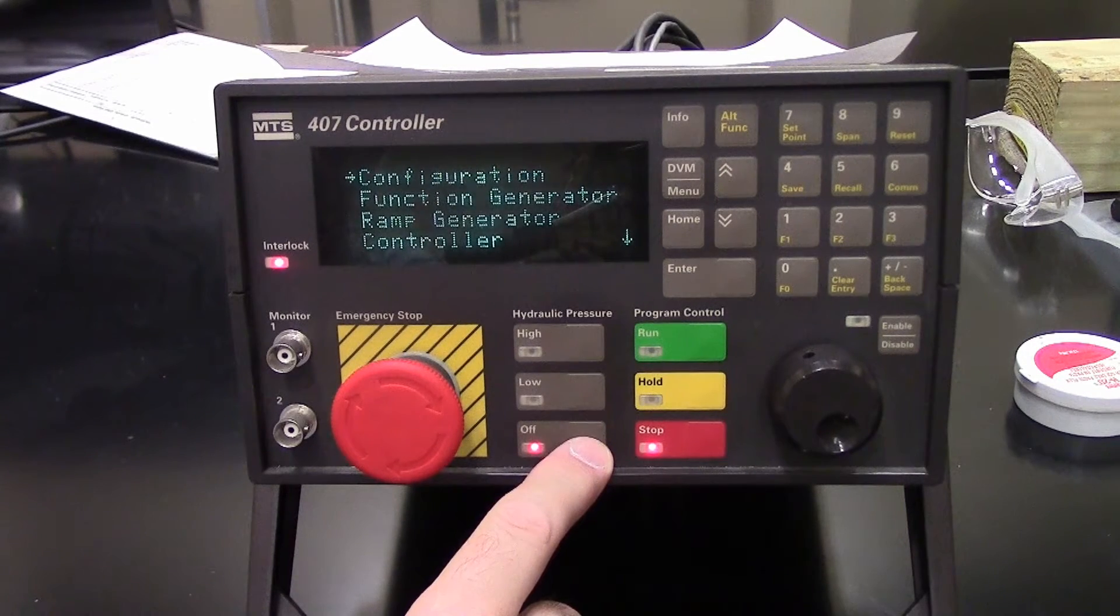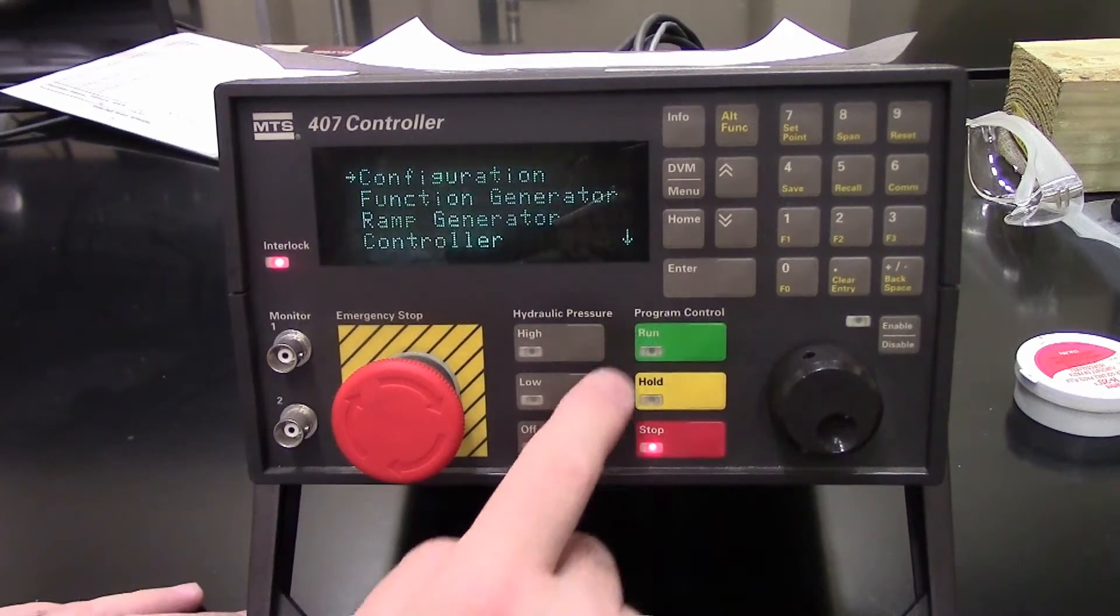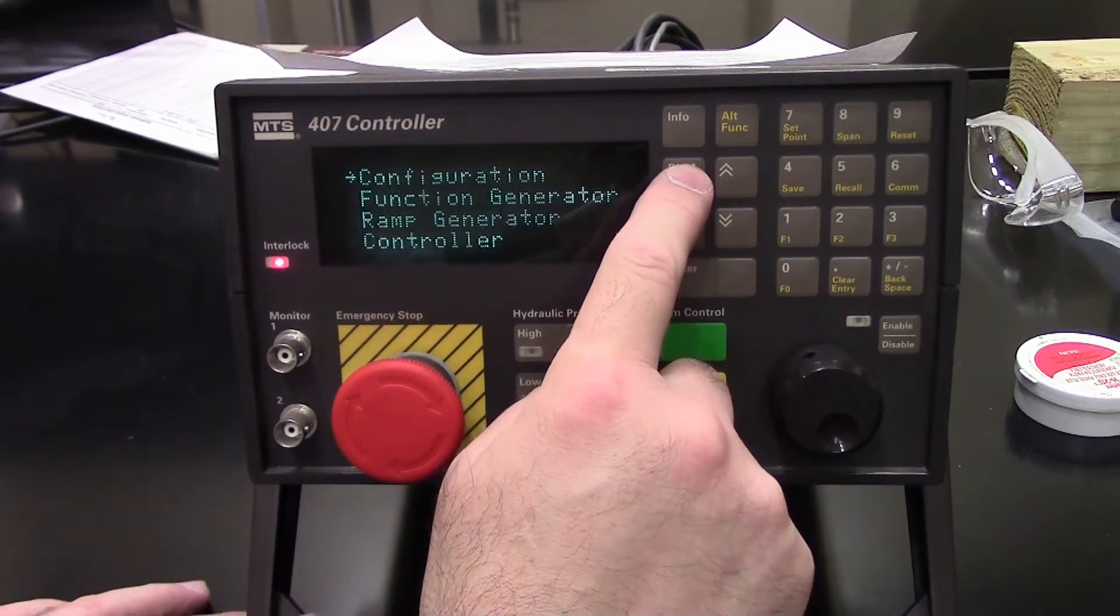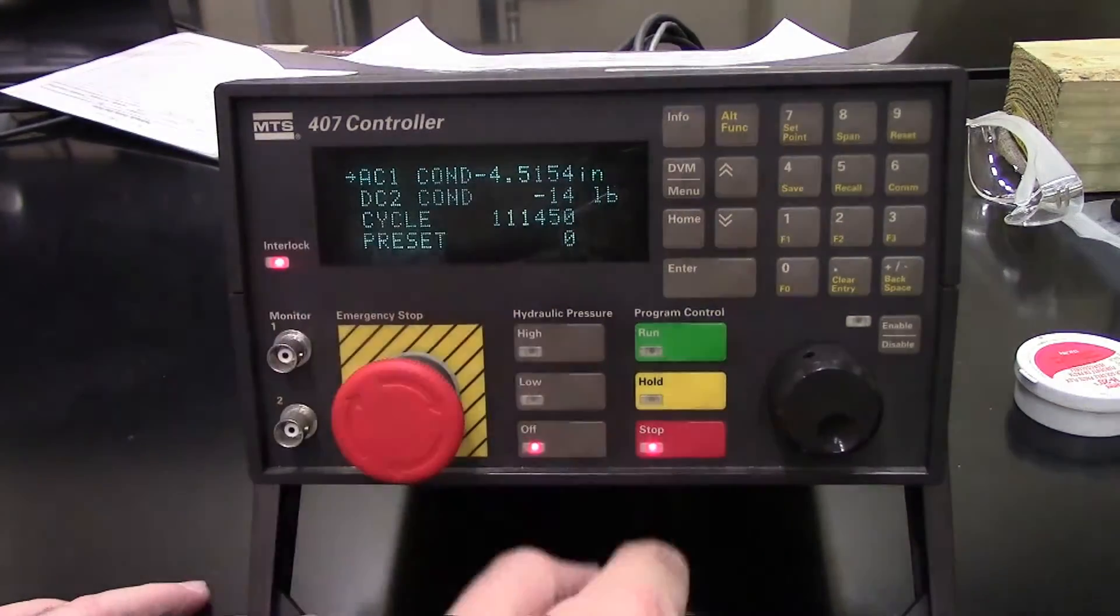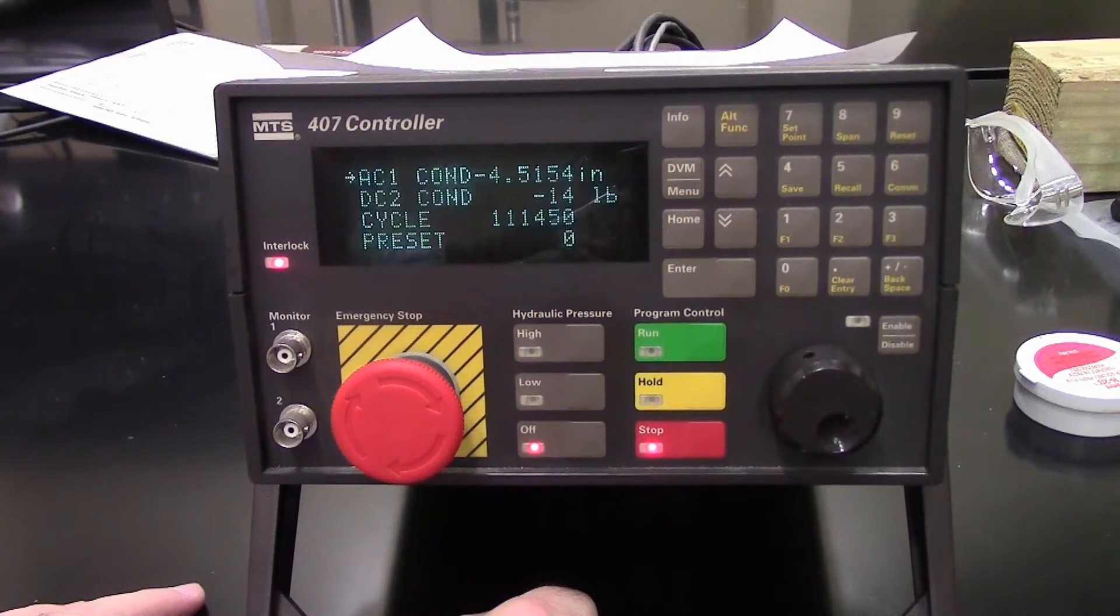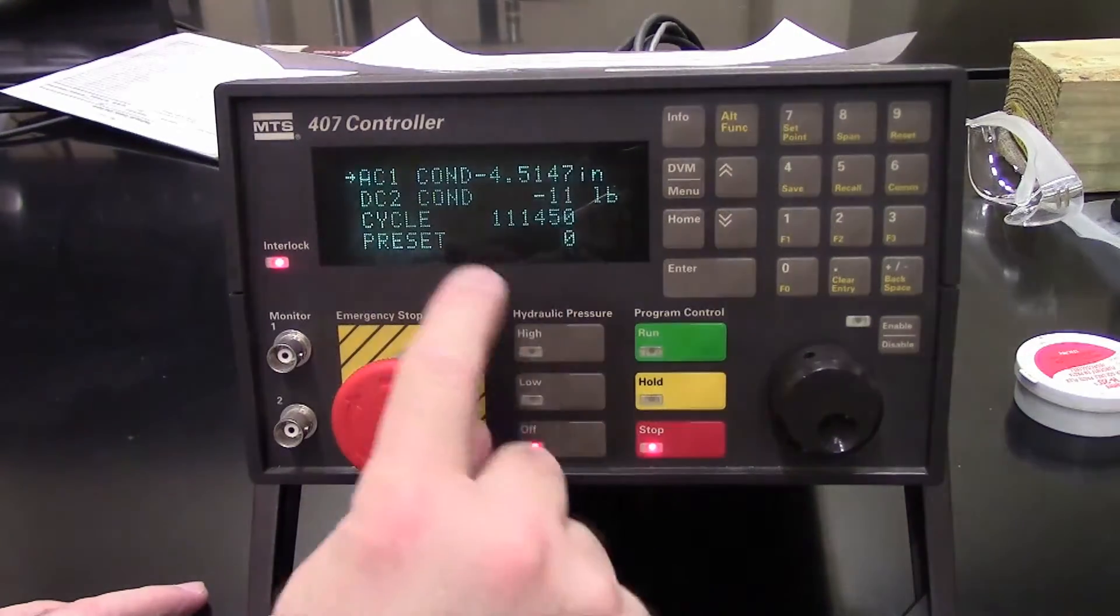I'm going to go through each of these menus. There are multiple menus, and there's what's called the menu and the DVM button. The DVM is a digital voltmeter. As you press this button, it'll swap between the current AC1 conditioner reading, which is displacement, the LVDT, and the DC2 conditioner, which is the load cell. Here's the cycle count.